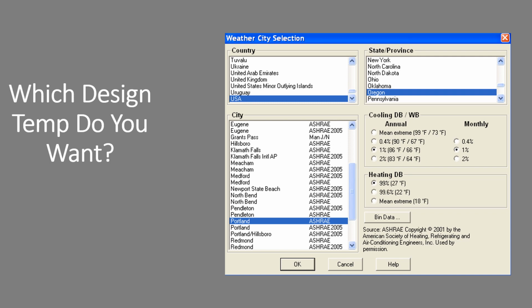Sure enough, only 1% of the time, historically speaking, has the summer design temperature been above 86. But your customers buy air conditioning for when it gets warm. And generally we see temperatures when people really use air conditioning around 95 degrees. My advice is don't be afraid of using the 0.4 cooling design temperature summer or the mean extreme.